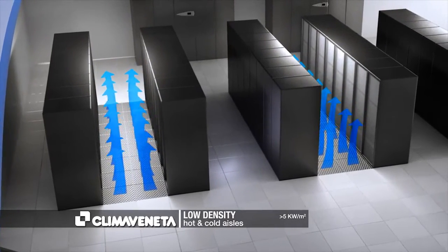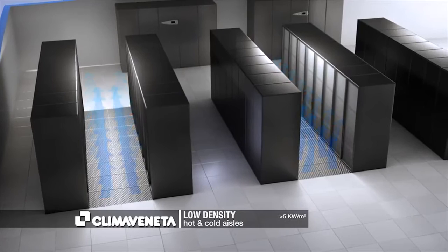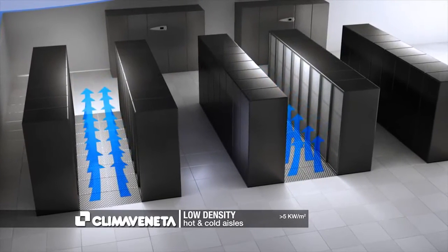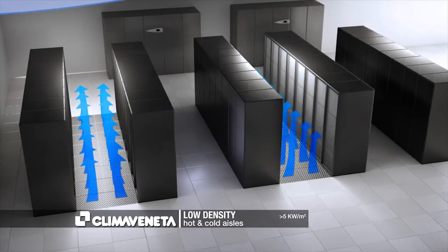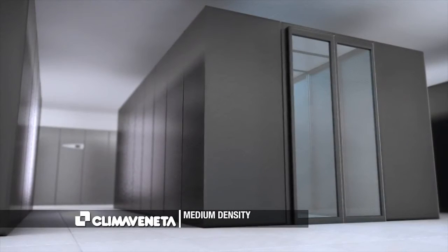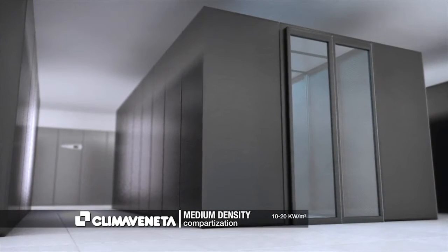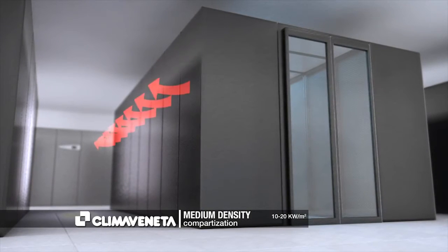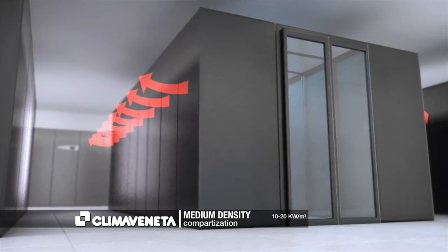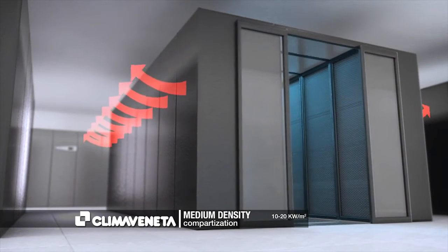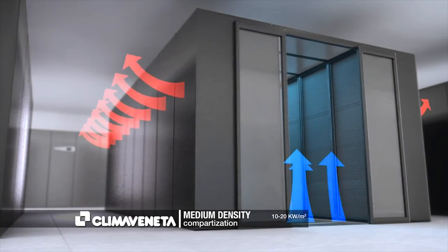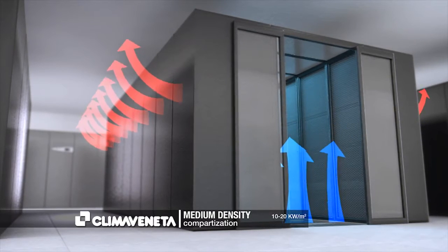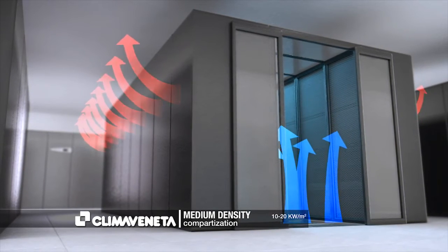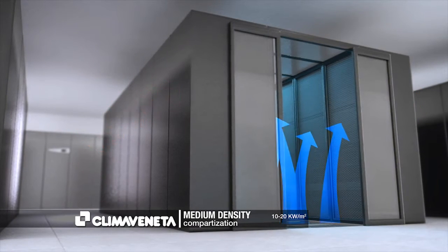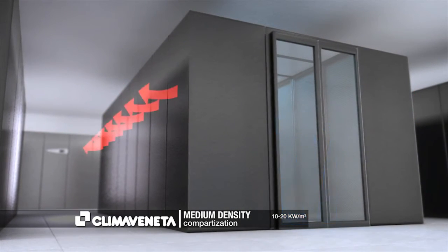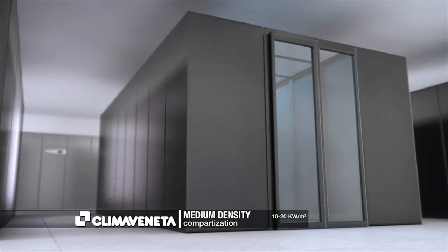This solution is simple. It requires minimal investment and is highly flexible, so that growth and expansion can be managed with little structural impact. The first evolution toward high-density applications can be achieved by medium-density aisles. Medium-density aisles are created by a containment system that concentrates the cold air from the floor to the rack and provides a constant and consistent airflow. This solution requires a low investment and provides additional energy savings up to 15%.